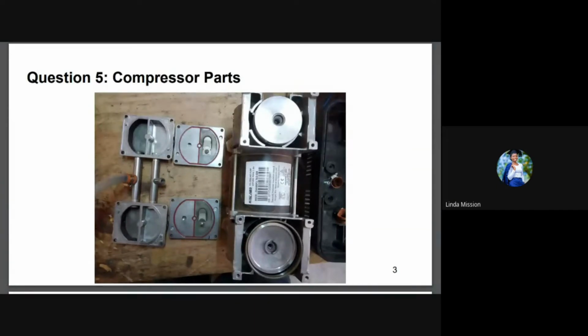When the piston moves down together with the piston cap, it creates a negative pressure, thereby sucking air from the outside. The air gets pulled into the cylinder sleeve through the inlet via the one-way valve on the inlet side. The one-way valve on the exhaust side prevents air in the exhaust path from being dragged back. And as the piston cap moves up, the one-way valve on the inlet side prevents the air in the cylinder sleeve from going back into the inlet. Rather, this air gets directed to the exhaust via the one-way valve on the exhaust side. For a 50 Hz electrical outlet, this process happens 50 times in a second. And this makes the compressor achieve the air compression necessary for sieving nitrogen in the sieve beds.